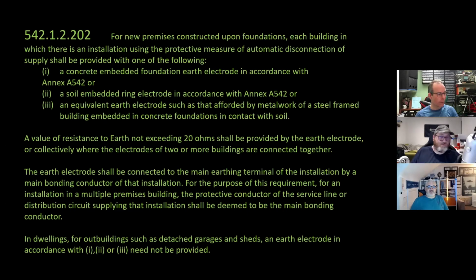A value of resistance to earth not exceeding 20 ohms shall be provided by the earth electrode, or collectively where the electrodes of 2 or more buildings are connected together. The earth electrode shall be connected to the main earthing terminal of the installation by a main bonding conductor of that installation. For the purpose of this requirement, for an installation in a multiple premises building, aka flats, the protective conductor of the service line or distribution circuit supplying that installation shall be deemed to be the main bonding conductor. In dwellings, for outbuildings such as detached garage and sheds, an earth electrode in accordance with 1, 2, or 3 need not be provided.